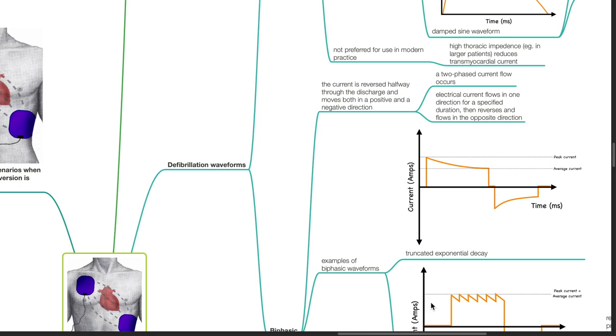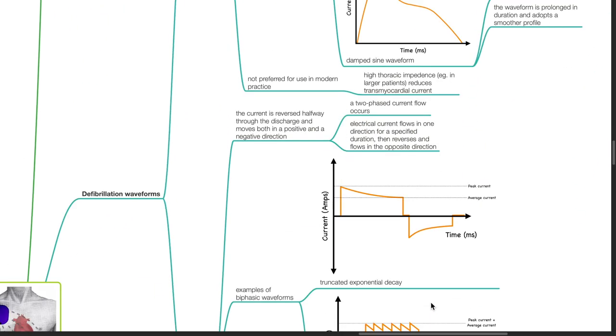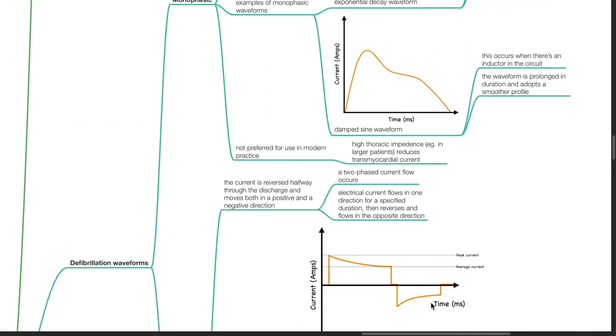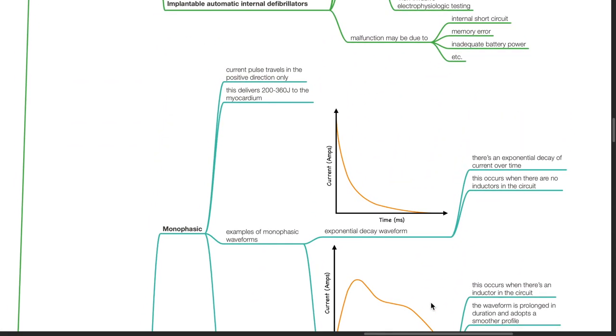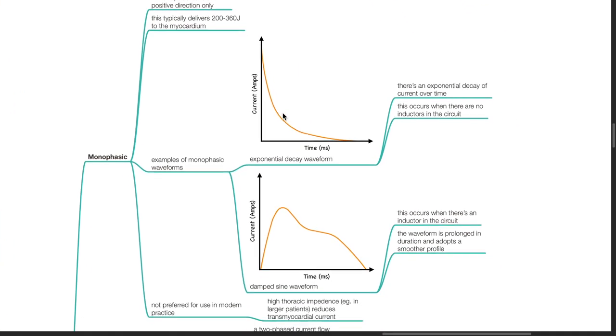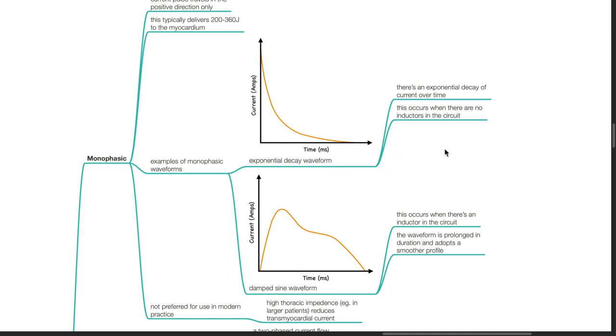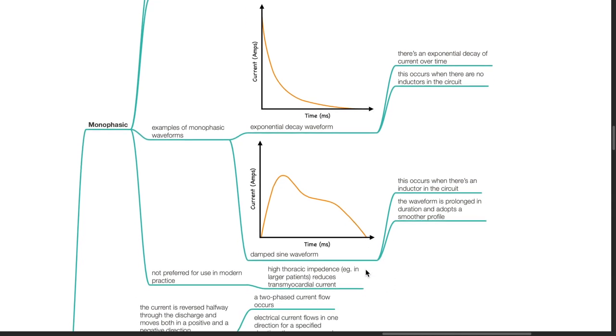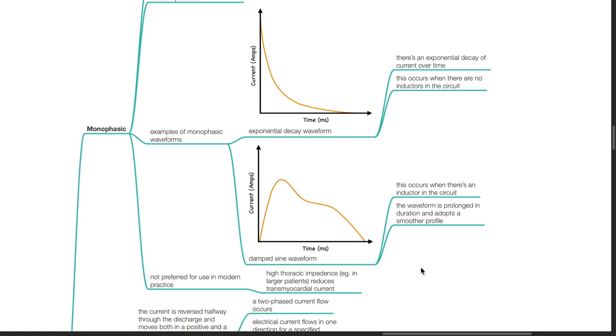Defibrillation waveforms can be divided into monophasic and biphasic. For monophasic waveform, the current pulse travels in the positive direction only, typically delivering 200 to 360 joules to the myocardium. Examples include exponential decay waveform, where there is an exponential decay of current over time occurring when there are no inductors in the circuit, and the damped sine waveform, which occurs when there is an inductor in the circuit and the waveform is prolonged in duration with a smoother profile. Monophasic waveforms are not preferred in modern practice.